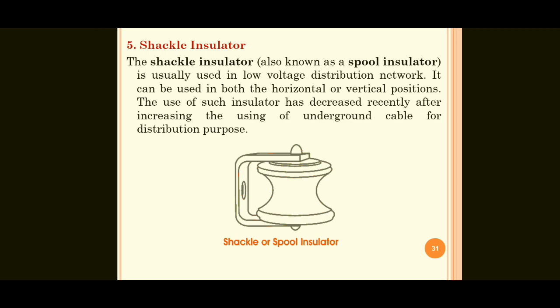So here, totally 5 types of insulators are present: pin, suspension, strain, stay and shackle insulators. Pin, suspension and strain insulators are used on the high voltage side. Stay insulator and shackle insulators are used on the low voltage side. The pin insulator has the capacity of 33 kilovolt. In the suspension type insulator, each disc has the voltage rating of 11 kV. So depending on the voltage rating, the number of discs connected varies.